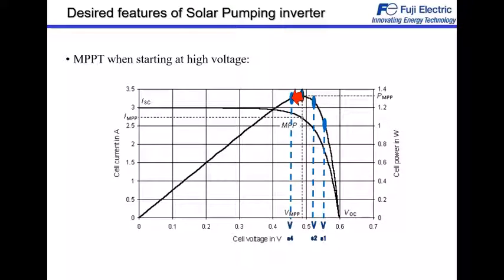It moves again and reduces the voltage. In this case, it may get a bit higher current, but at the end the output power is lower. So the drive recognizes that this is not the best point, the maximum power point, and moves back to the previous point and stays there. And the drive is continuously searching for this point.